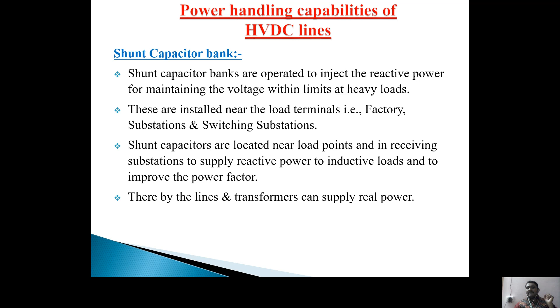You already know we have three types of loads: a resistive load, a capacitive load, and an inductive load. The resistive load is a linear load, the capacitive load is a leading load, and the inductive load is a lagging load. Any factory and switching substation gives a lagging power factor, that is, the inductive load. Shunt capacitors are located near the load points and in receiving substations to supply reactive power to inductive loads and to improve the power factor, thereby the lines and transformers can supply the real power.